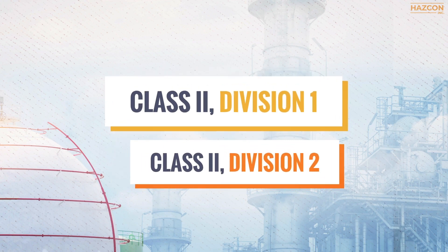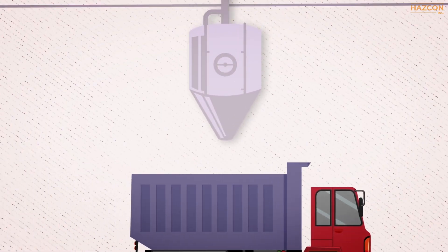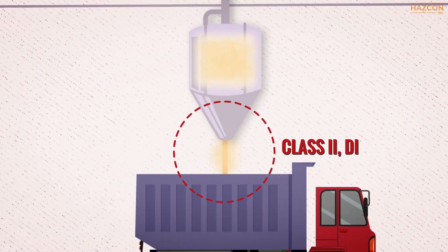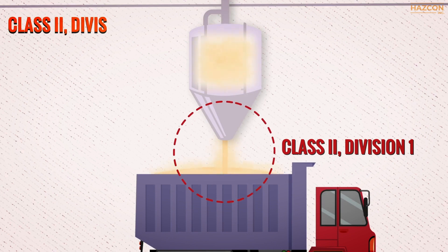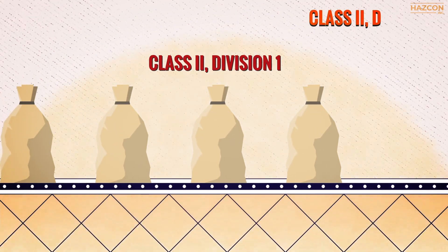In this animation, we will focus on the Class/Division system classification of dust explosive atmospheres — specifically Class 2 Division 1. Class 2 Division 1 is defined as a location in which combustible and explosive dusts are in the air under normal operating conditions and in quantities sufficient to produce explosive or ignitable mixtures.